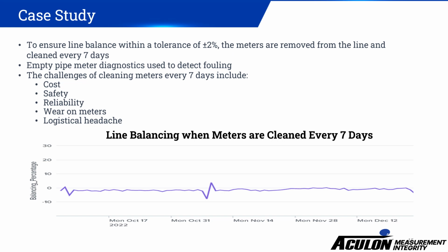To ensure optimal line balancing within a tolerance of plus or minus 2%, meters were removed from the line and cleaned on a 7-day interval, as 9+ days started to see drastic increases in line balancing and affecting leak detection. Other tools used to determine dirty meters were also meter diagnostics or empty pipe, as fouling on the electrodes caused lower resistance and lower volume readings on each of the meters that were affected by coating or buildup.